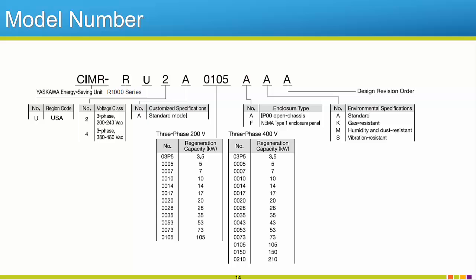Yaskawa has always tried to keep consistency at the forefront. Whether it be consistency in quality, product lineups, or even something as simple as the model number. For those of you familiar with Yaskawa's 1000 series lineup, this model number breakdown should be nothing new. The R will naturally designate the unit as an R1000. Following that, there will be a region code, a voltage class, and also a spec. In addition to the voltage class, one of the most important designators is the rated capacity. This value is in kilowatts and designates how much regenerative power that specific R1000 is rated for. This differs from our drives, which are rated for an output current. The last three designators will determine the chassis type, any added environmental specs, and the revision of the unit.